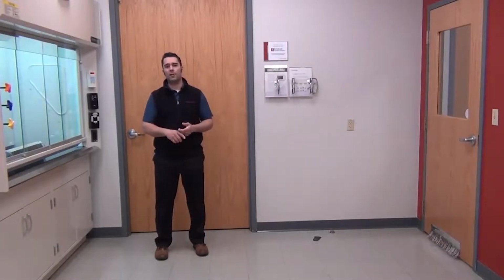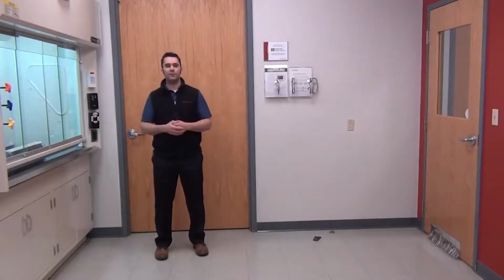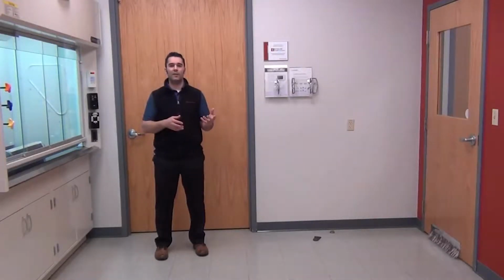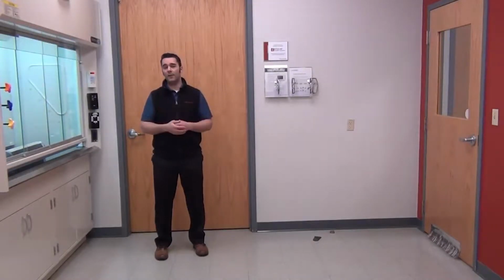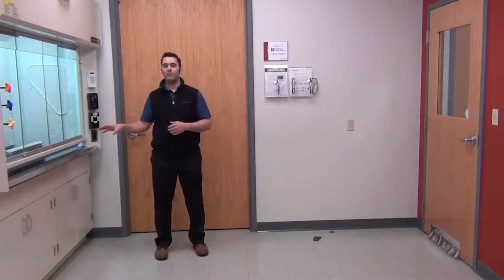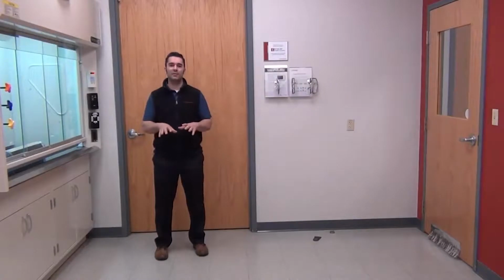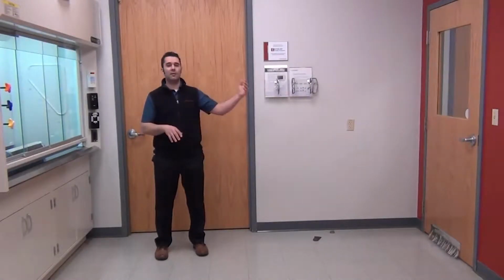They're much lower cost, and they're a little bit easier for somebody else that doesn't know much about airflow controls to configure. You just drop a K-factor into them and you measure the airflow and you're good to go. The problem with that is the reaction of those devices to the 1-second speed of response of a fume hood does not guarantee the pressurization in this space to stay stable. It also does not guarantee that the adjacent spaces will be stable either.